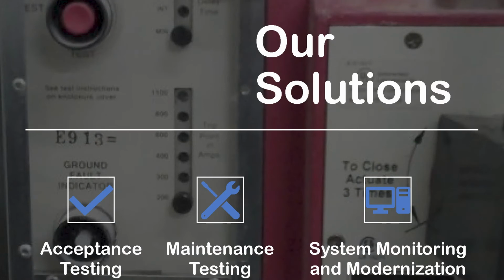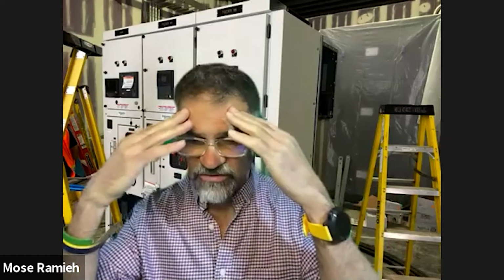I get a call at least once a month from somebody that hasn't had a problem for 10 or 15 years. And last week they had something fail that caused an unplanned outage that caused them some frustration. And now this week they'd like to start monitoring their system so they can figure out what happened. And to me, that's just mind blowing, because you hadn't had a problem for 10 years. You had a problem last week. What makes you think you're going to have a problem this week or next week or next month or the next 6 months? So once again, me coming in with temporary monitoring is always, I think, a poor solution. We're putting a Band-Aid on the symptom, not actually attacking the problem.